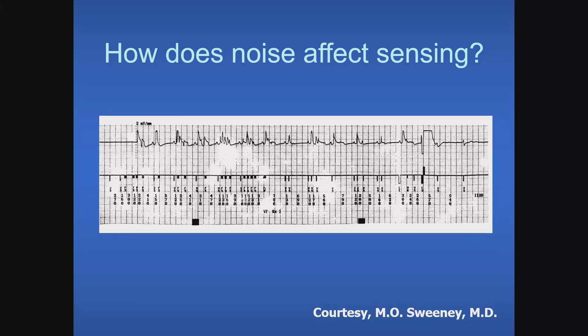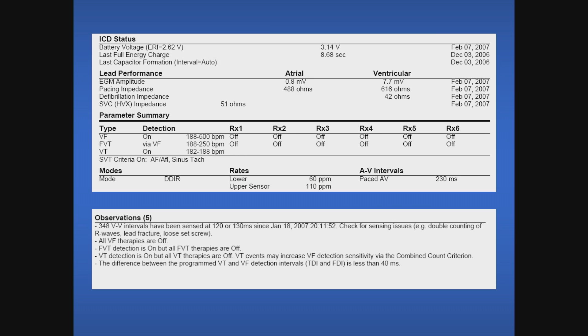A lot of the defibrillator systems now have early warning systems for defibrillator wire fracture. So you notice here on this slide that I show you that it is noticed that there are very, very short VV intervals that have been sensed at 120 or 130 milliseconds. These are very, very short intervals that are very likely to be electrical noise rather than a biological event from inside the heart. And it's important to recognize that these are likely due to a defibrillator wire failure rather than a true arrhythmia.